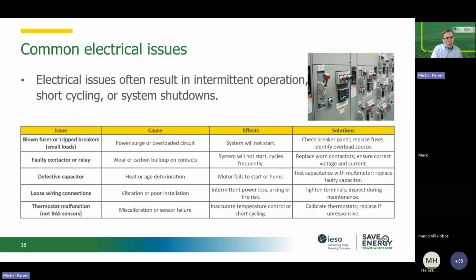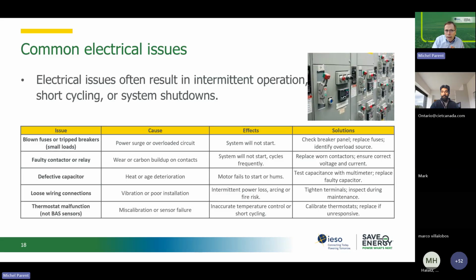Again, you will know the cause of it, and you can know what the effect is as an operating team. But when you get to the solution, you will not do that. You will get an electrician to do that for you. So if the system starts to fail to start, short cycles frequently, very likely it's going to be the contactor, the relays, that need to be changed. What this little table provides you is really a quick diagnostic tool. Say, hey, I hear this humming from this motor, and it sometimes fails to start. That is likely the capacitor that is problematic.